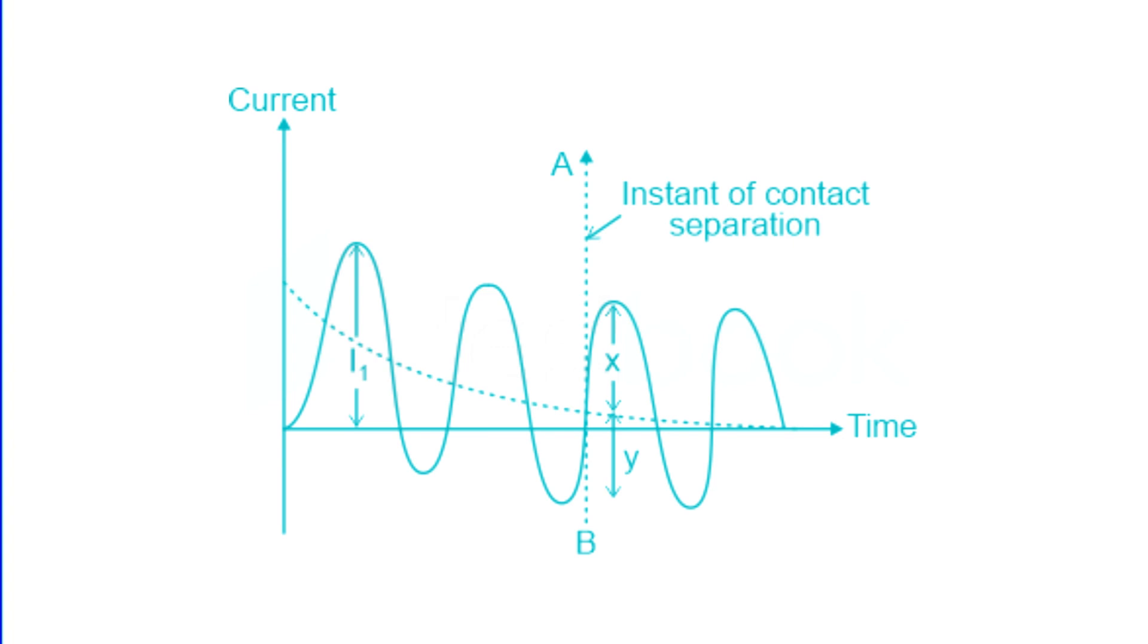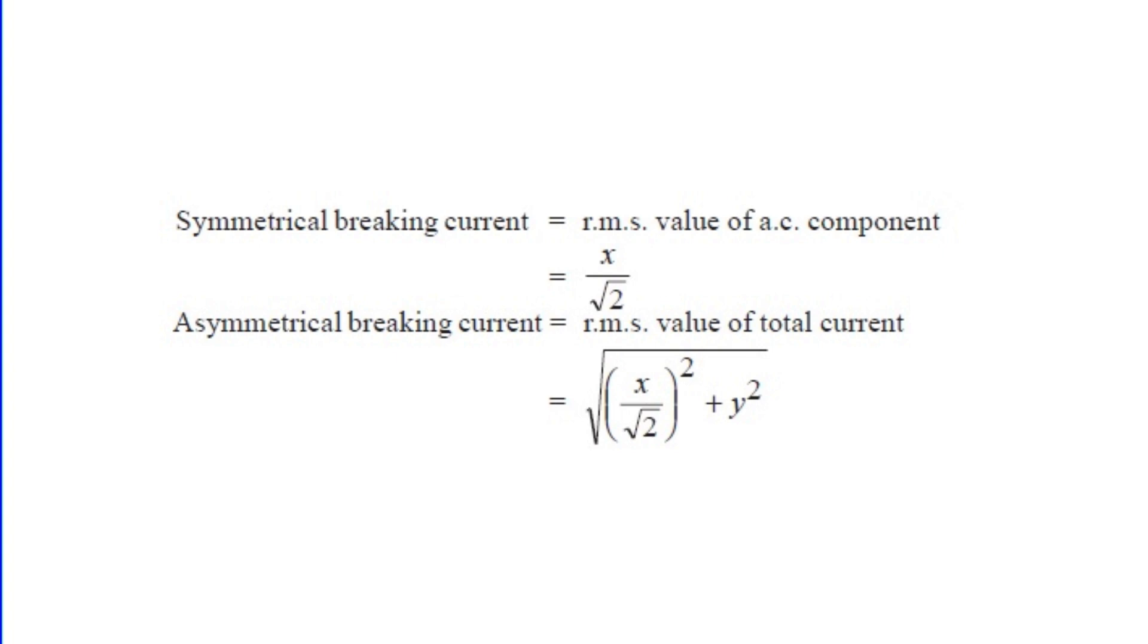At this point, let the symmetric component of the current be x ampere and the DC component be y ampere. Therefore, the symmetrical breaking current is equal to the RMS value of the AC component, that is x by root 2, and asymmetrical breaking current is equal to the RMS value of the total current.